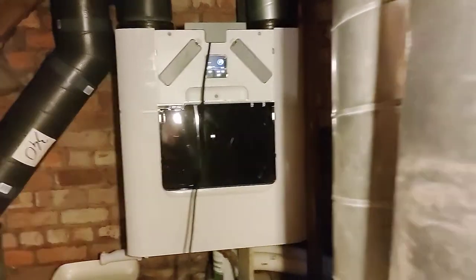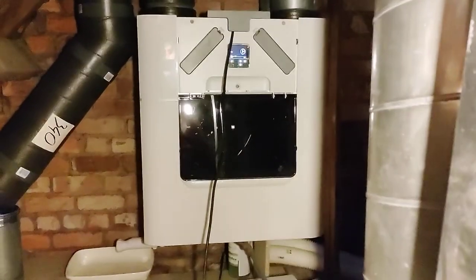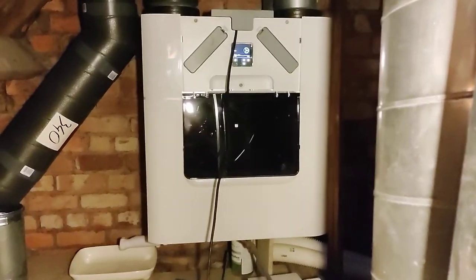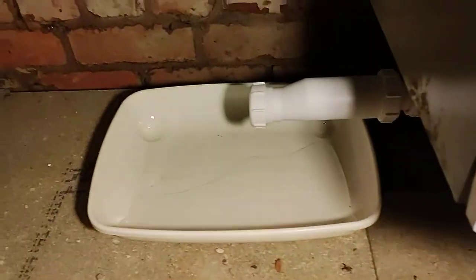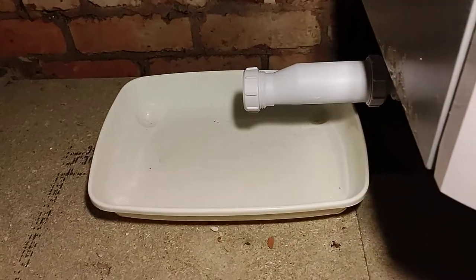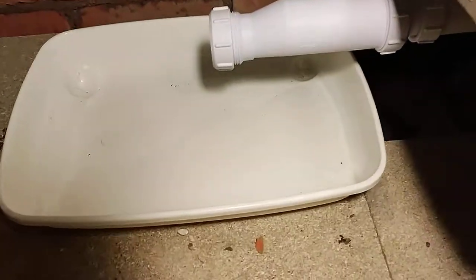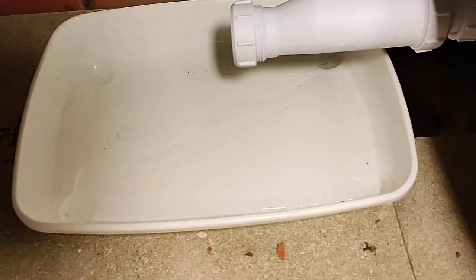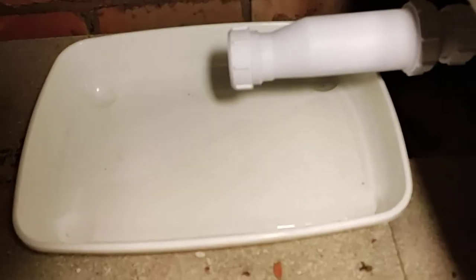A few months ago, I connected up the MVHR system in this property, and I connected up the condensate drain. But if you see, it's a dry trap, and I didn't connect it to a wastewater pipe because I wanted to do a little experiment and see how much water would come out of the system.